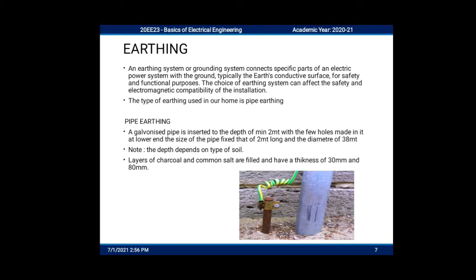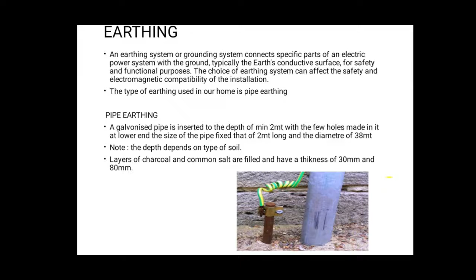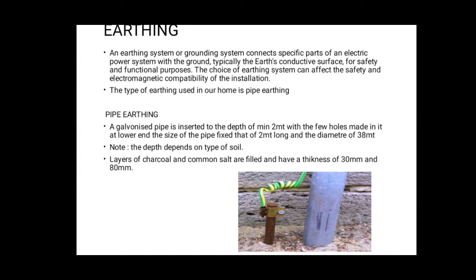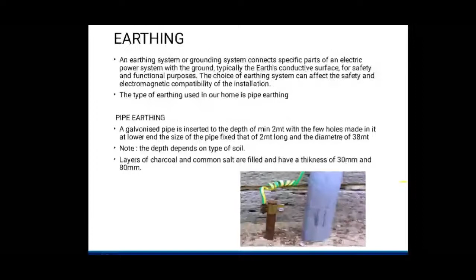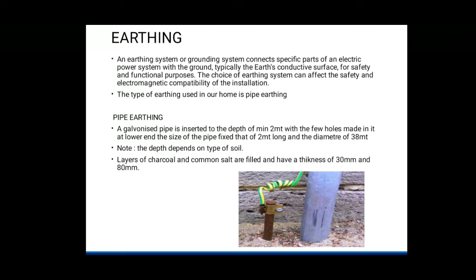Earthing system or grounding system connects specific parts of an electrical power system with the ground, typically the Earth's conductive surface, for safety and functional purposes. The choice of earthing system can affect the safety and electromagnetic compatibility of the installation. In my home, the type of earthing is pipe earthing. In pipe earthing, a galvanized pipe is inserted to a depth of minimum 2 meters with a few holes made in it at the lower end. The size of the pipe fixed is 2 meters long, and the diameter is 38 mm. The depth depends on the type of the soil. Layers of charcoal and common salt are filled, with thickness of 30 mm and 80 mm.